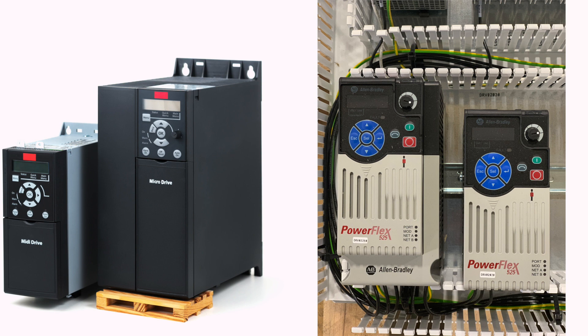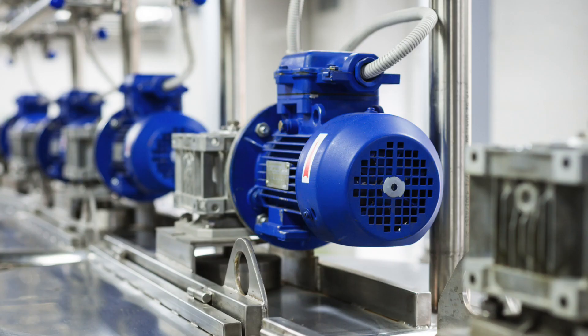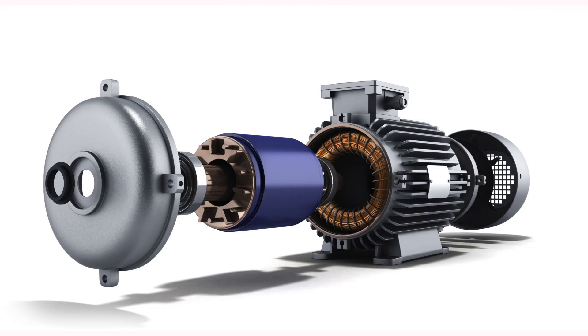Some of the most common AC motor is known as the squirrel cage motor. The name comes from the aluminum or copper squirrel cage embedded within the iron laminate of the rotor. Note that there is no physical electrical connection to the squirrel cage. The current in the rotor is induced by the rotating magnetic field of the stator.